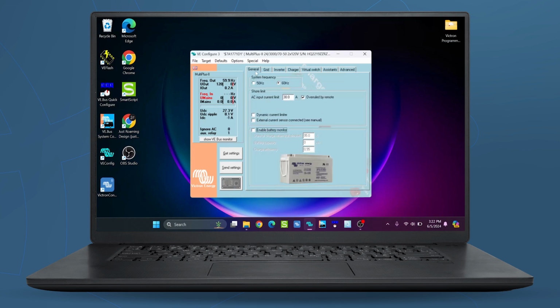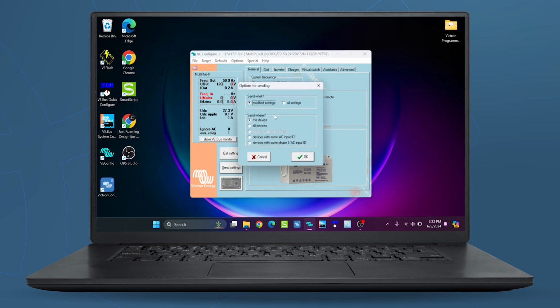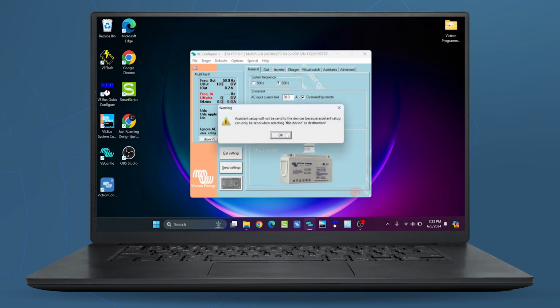Once you've configured those two settings in the General and the Charger tab for specifically the Lynx BMS system, we need to send those settings to the inverters, so we're going to click on Send Settings. We're going to select Modified Settings, and then select all devices so that we configure both devices at the same time. We can click OK, and it's going to send those settings over.